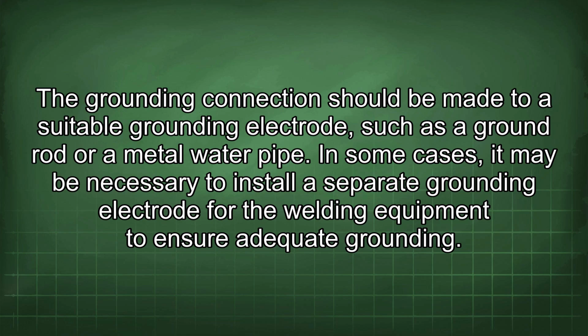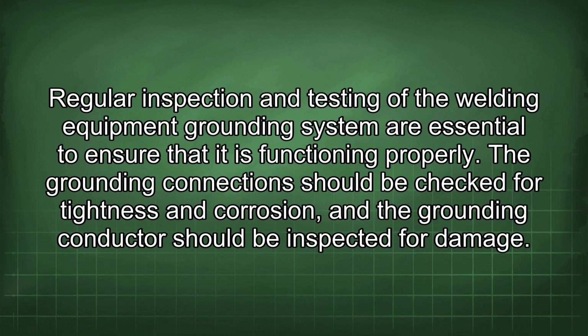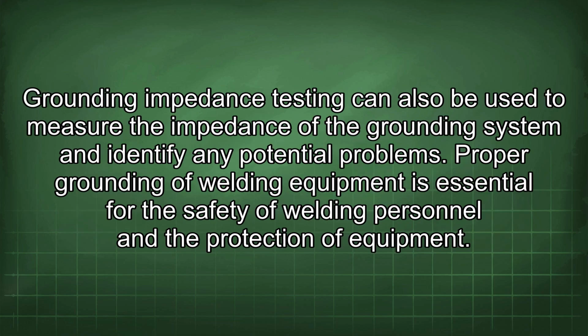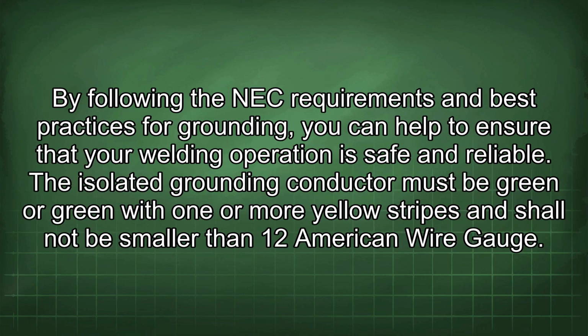to ensure adequate grounding. Regular inspection and testing of the welding equipment grounding system are essential to ensure that it is functioning properly. The grounding connection should be checked for tightness and corrosion, and the grounding conductor should be inspected for damage. Grounding impedance testing can also be used to measure the impedance of the grounding system and identify any potential problems. Proper grounding of welding equipment is essential for the safety of welding personnel and the protection of equipment.